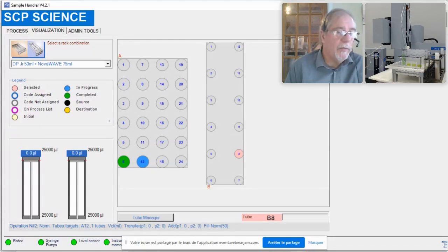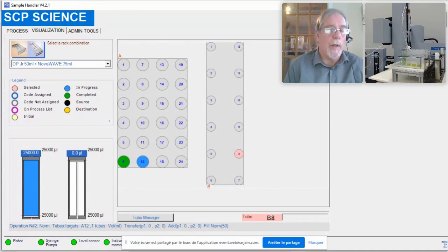sensor. So there we've done the first tube, and we use a color coding scheme here to say green is when it's completed, blue when it's in progress. When you're doing dilutions and aliquoting, we use different colors to control the legend so that when you get used to it, once the system is in your facility, you'll be able to visualize as you walk by the screen to control things. We use a computer with Windows 10 for the control of the system. So this allows you to save your methods. It allows you to pull them up, to manipulate, to configure it to any rack configuration as required.